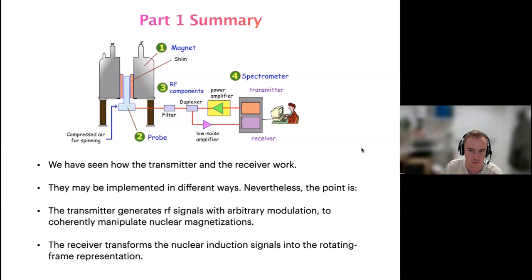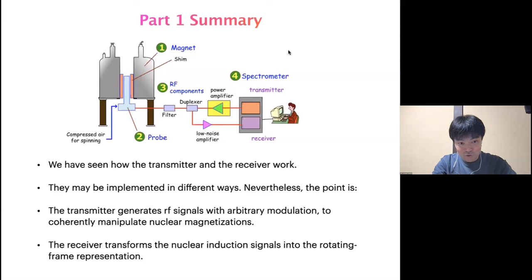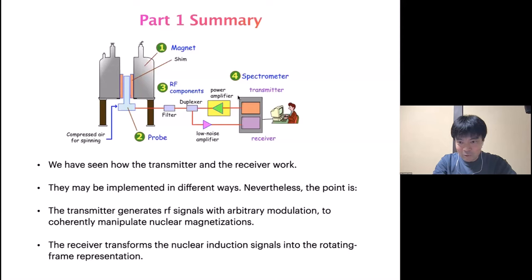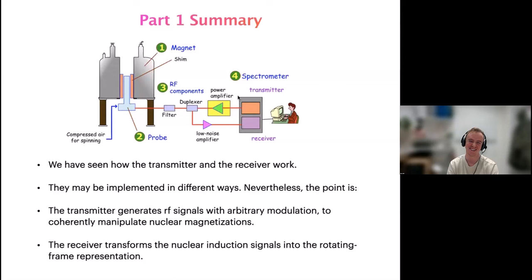Is there an absolute signal-to-noise standard in NMR? That's a very difficult question and I don't have a good answer. Rather than the spectrometer itself, it's the probe and low-noise amplifier — in particular the first-stage LNA — that determines the overall signal-to-noise ratio. I'm interested in characterizing the noise performance in terms of power spectral density, but we are procrastinating on that.